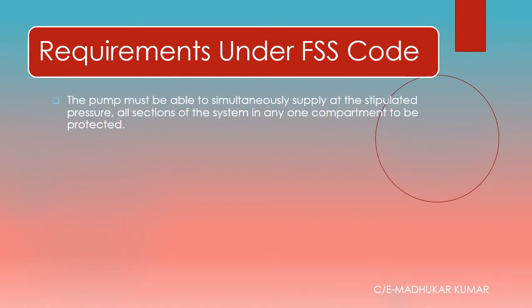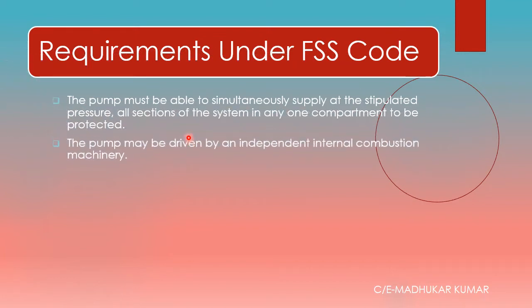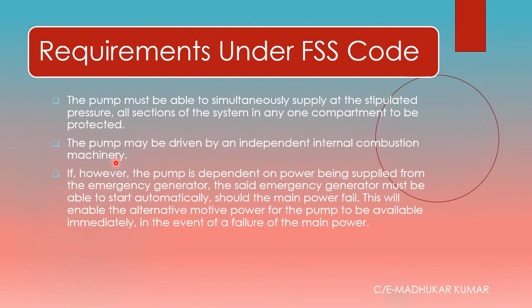The pump must be able to simultaneously supply water at the stipulated design pressure across all sections of the system in any one compartment to be protected. The pump may be driven by an independent internal combustion engine, but normally the main power supply is used, with an internal combustion engine as a backup.